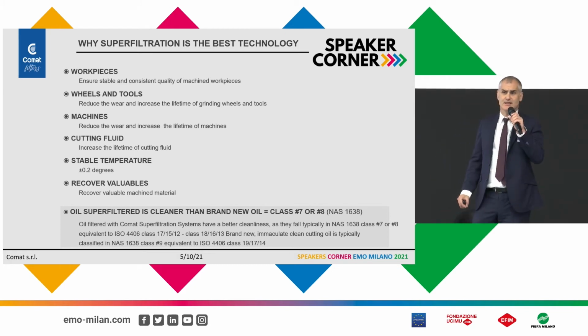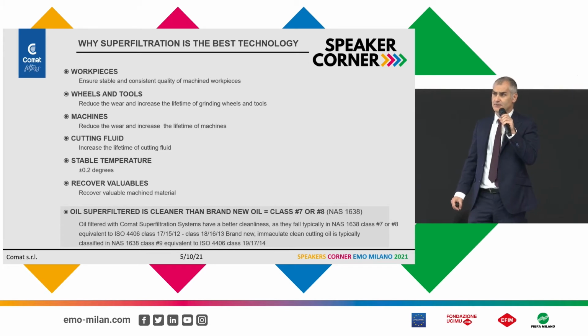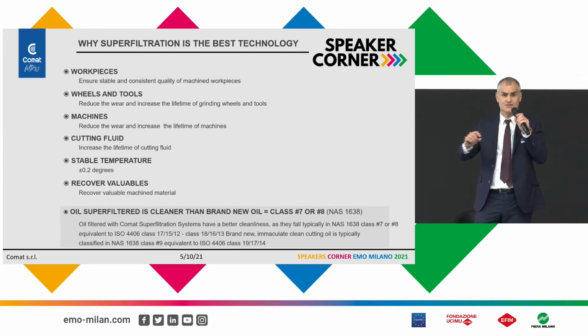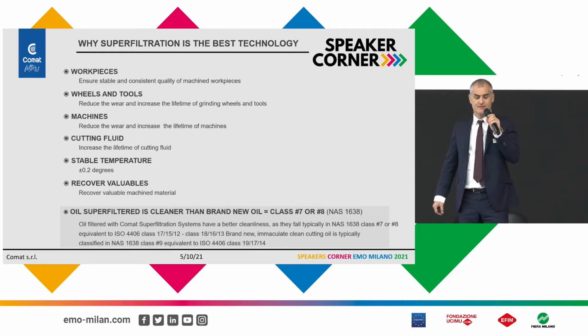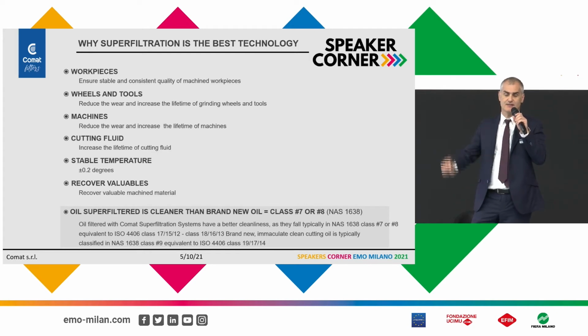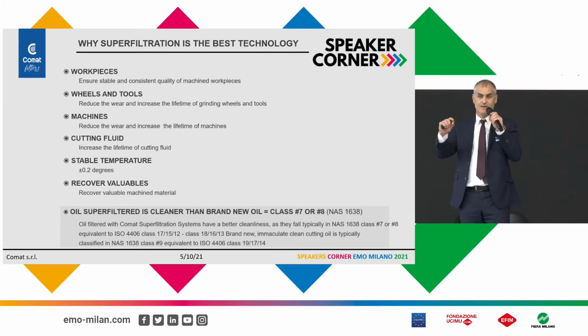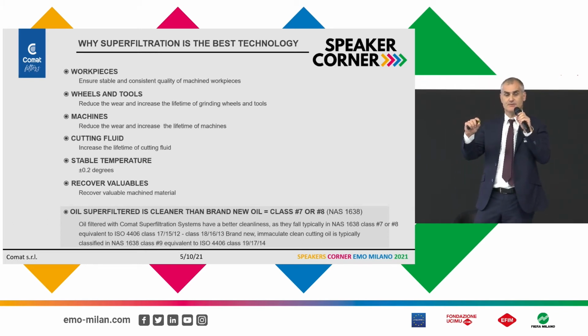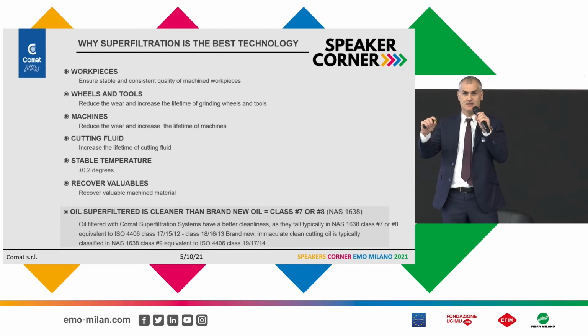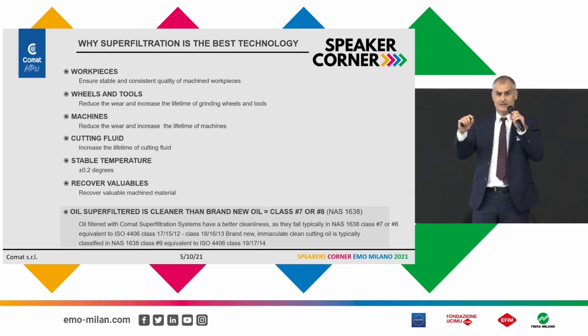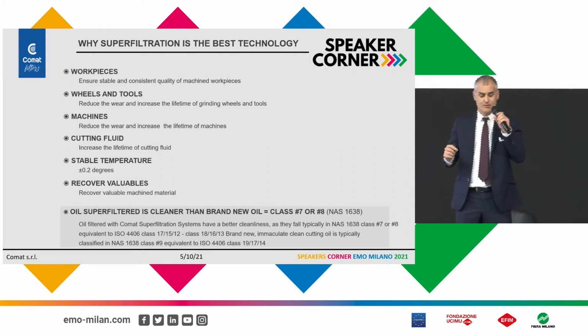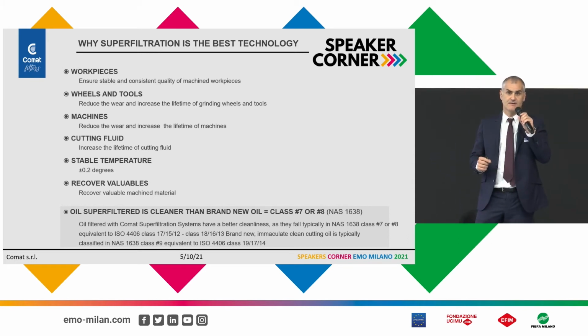We can increase significantly the lifetime of the cutting fluid. We have certain clients that haven't changed the oil for 10 years. They just refill the oil that is dispersed through the machining, but the quality remains so high that the oil can be reused for several years. We manage to maintain very stable temperatures using PID technology in our chillers. We can achieve a tolerance of plus or minus 0.2 degrees. That clearly is also an essential feature to achieve high quality machining.